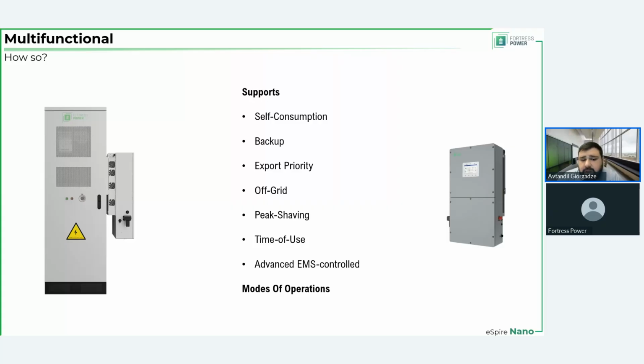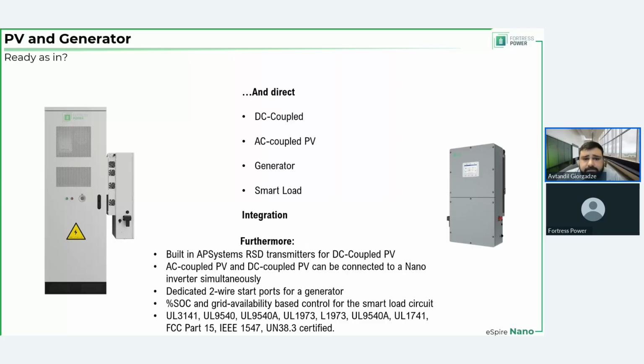But I can tell you right now that advanced EMS-controlled operation means that you can do an even more complex peak shaving strategy. You can do an even more complex and more specific time of use schedule. And you can also monitor external circuits, and you can have AC coupled PV remote from the inverter and still monitor it and still control it. That is what the EMS-controlled operation brings to the table as a value proposition.